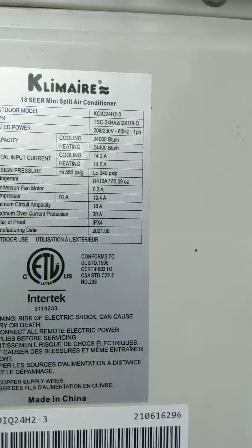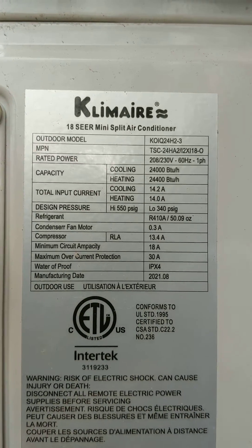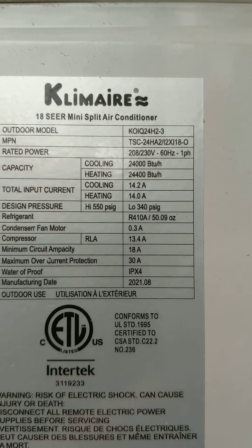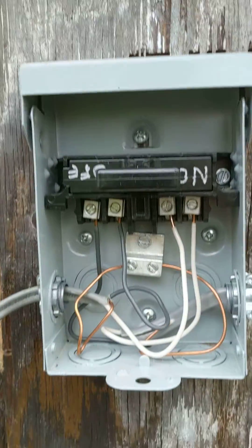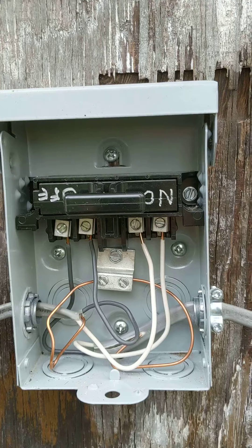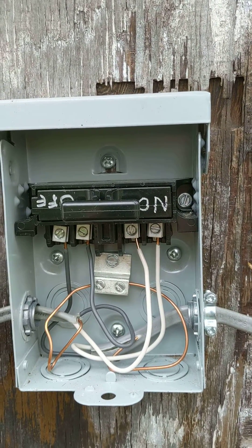Let me start off by showing you the amperage. This is the 24,000 BTU or two-ton Klimaire mini split. It is 240 volts. Hopefully you can see that it is 14 amps that it requires. This is a minimum circuit capacity of 18 amps, so we are running this off a two-pole 20 amp breaker.